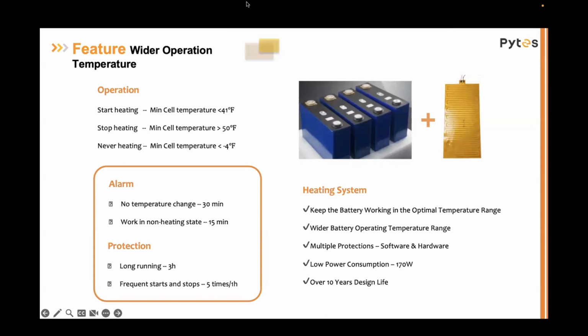Some more details about our heating pad: it takes 170 watts of power, the maximum output needed to keep the batteries heating. This temperature is calculated by the BMS inside the V5. When the V5 reads that the ambient cell temperature is below 41 degrees Fahrenheit, the heating pad kicks on, and it'll stay on until the battery reaches 50 degrees Fahrenheit, then it kicks off. Also, the minimum threshold where the heating pad will still work is -4 degrees Fahrenheit—anything above that, the heating pad will function. Some more notes here on the alarms.